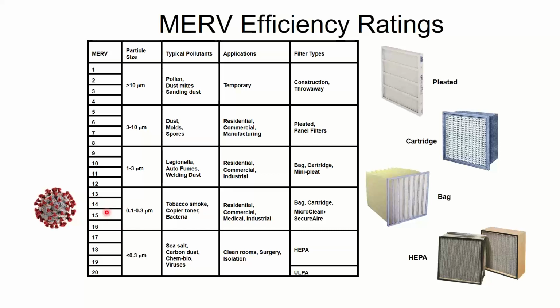But unless you're doing MERV 13 or 14, it's doing nothing. So if your building has MERV 6 or MERV 8 filters, which is pretty standard for a lot of air handling equipment, it's catching dust and keeping it off the coil, and that's its job in life, but it's not doing anything for your air quality. It's not even catching bacteria, let alone viruses. If you beef it up to MERV 10 or 12, you're getting some bacteria caught, but still nothing for viruses. You need to get to 13 or 14 to have a chance at catching COVID, and higher than that, MERV 15 and greater, if you want to start catching smaller viruses like influenza.